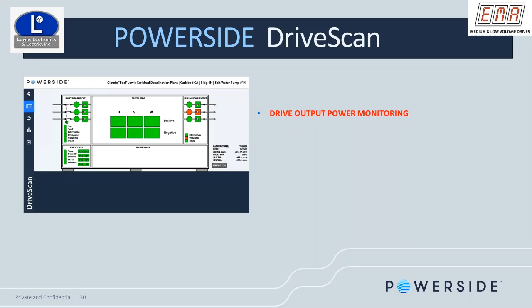We can look at input power and then output power, same scenario. If we lose an output module, we'll have a single phase going out of the drive, or if we have a loose connection, our current will be imbalanced. Some of these things we can see without drilling into the actual data, just by visually looking at the cloud-based software.